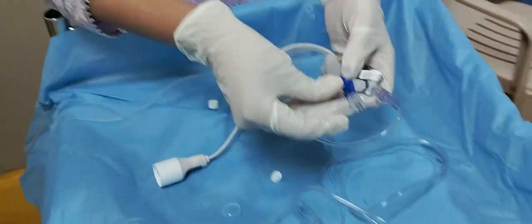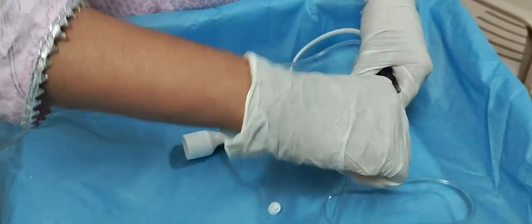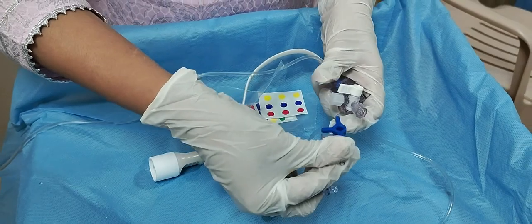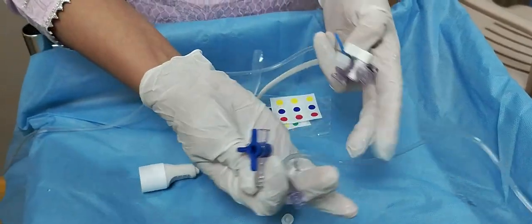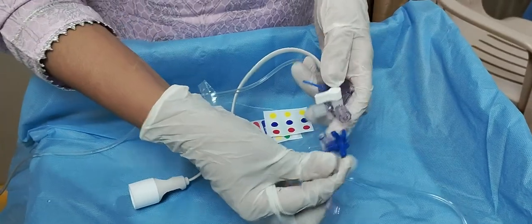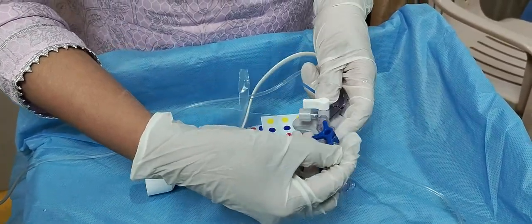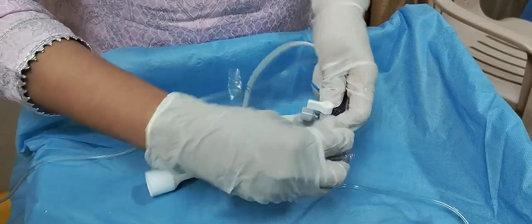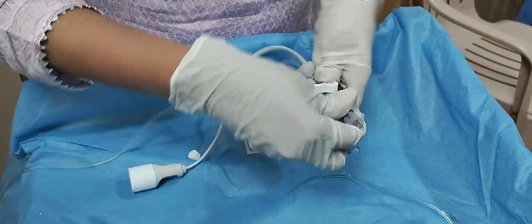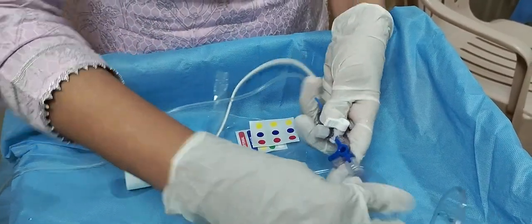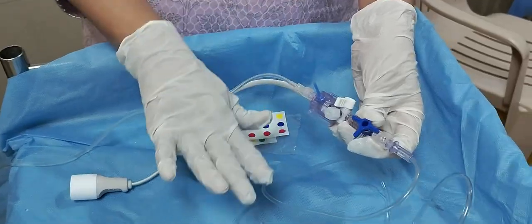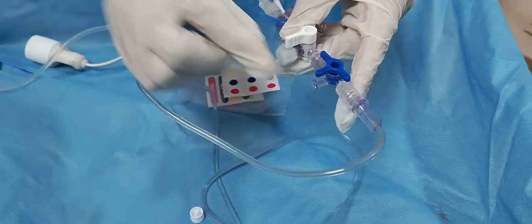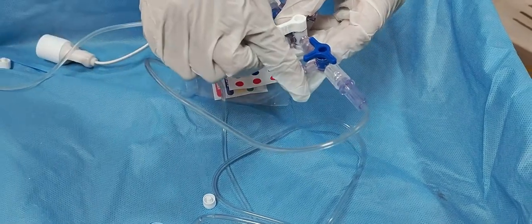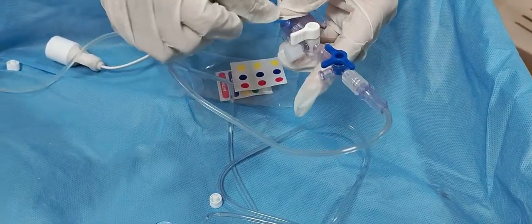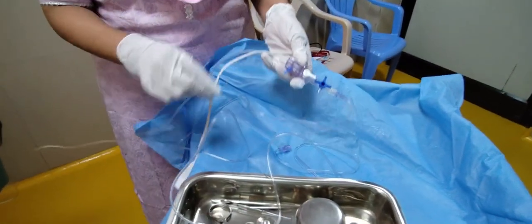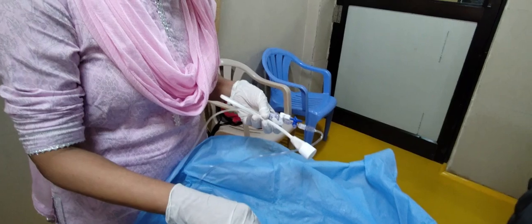It is also a good idea to connect the three-way. Where we should connect the three-way is in between the high pressure monitoring tube and the pressure gauge. So connect the three-way and make sure that the three-way is also flushed. This three-way is to have the heparinized saline. So the heparinized saline will be connected here, and the infusion will go constantly. Flush the system. The next important process is to do the leveling and zeroing.